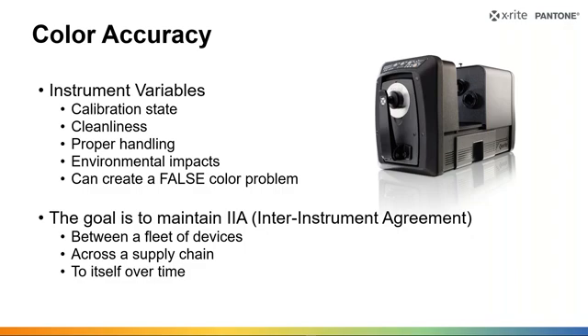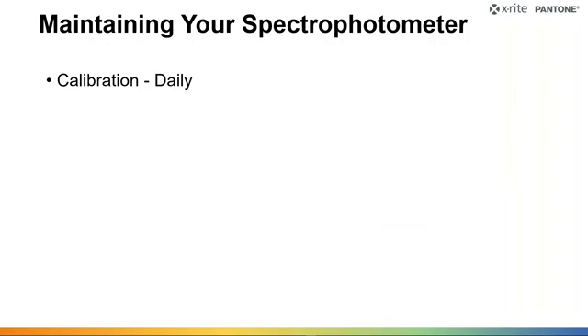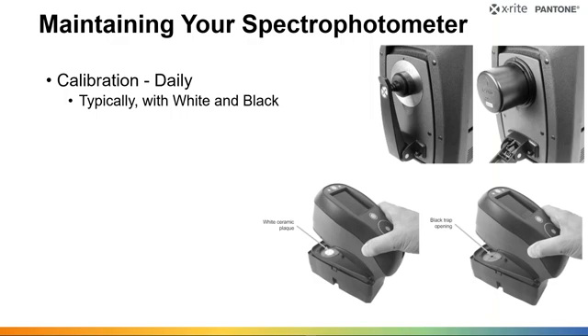So how do we go and deal with those? Well, number one is calibration. It's pretty standard and straightforward. The devices and software will force you to do this. Typically, they're with white and black, right? If you have a benchtop, the pictures on the top will look familiar. If you have a handheld, the pictures on the bottom might look familiar, right? So you're measuring a white, you're measuring a black, and what does that do? Well, it does two things: confirms and adjusts. It confirms that your instrument is still maintaining and living within its reflectivity limits. White being the most reflective thing, black or a light trap is really what those black things are, right? As zero, so I know what 0 and 100 are, and then I can calibrate and function within them.